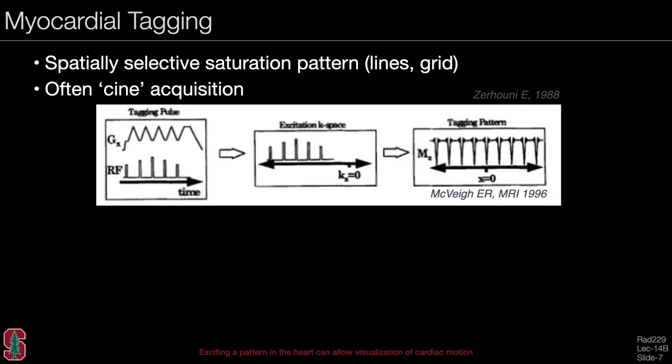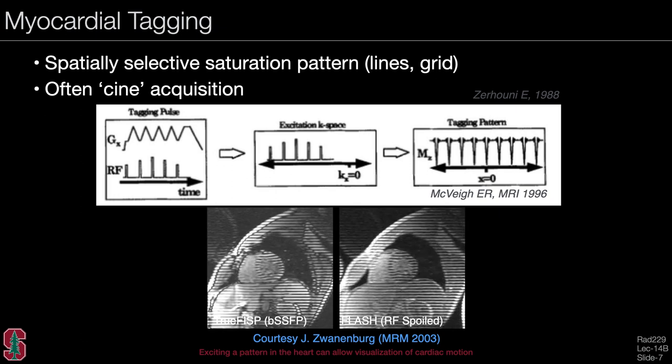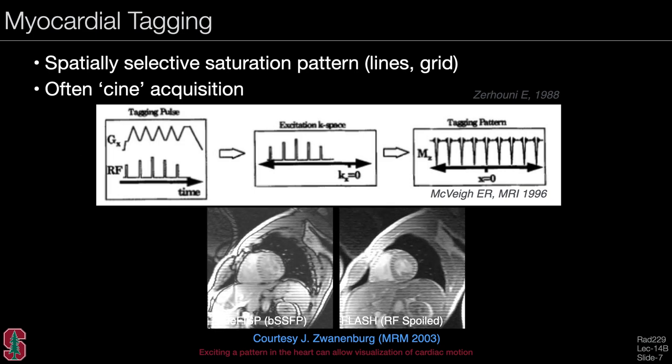Another very interesting form of saturation is myocardial tagging. You can saturate lines or a grid in the image by taking the RF pulse and breaking it into a comb function, so the excited pattern has this periodicity. This is often combined with a cine acquisition to look at the heart. Example images show a balanced SSFP approach where you can see lines in the heart and the myocardium moving. The tags wear off as the signal approaches steady state over the course of the heartbeat. You can also use an RF-spoiled or FLASH approach for a slightly different contrast, and the best choice may depend on the application.